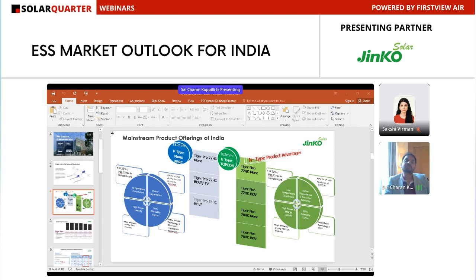But if the system requirement is going to stand at 500 megawatt hours, definitely AC coupled systems make more sense when compared with DC coupled systems. Also the most important aspect is that the entire ecosystem is completely following the trend of AC coupled systems, so the kind of safety configured materials or composite infrastructure specific to the AC side is completely well equipped when compared with DC kind of systems.